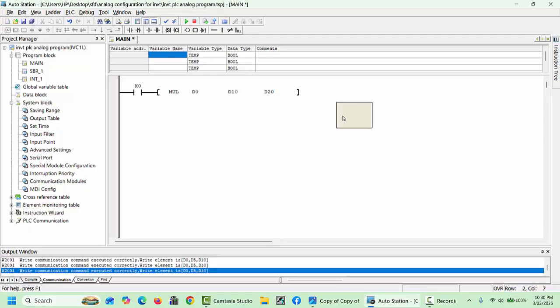For example, you are using an analog signal and would like to write the value from the HMI to your VFD, and you want the real value typed, meaning 10 Hertz, 20 Hertz, 30 Hertz, up to 50 Hertz, but 50 Hertz equals 10,000 bits inside the VFD. So typing the direct 10,000 from the HMI would be not very readable. So you have to use the multiplication command to type the value 10 into your VFD for the 10,000.